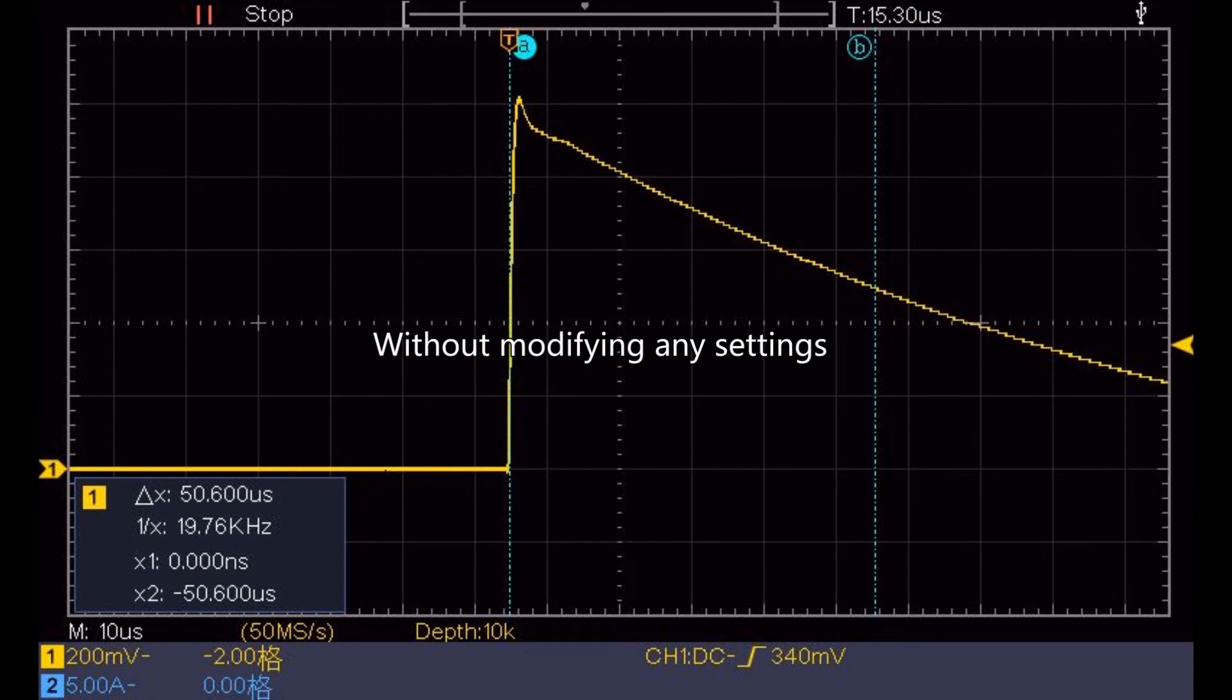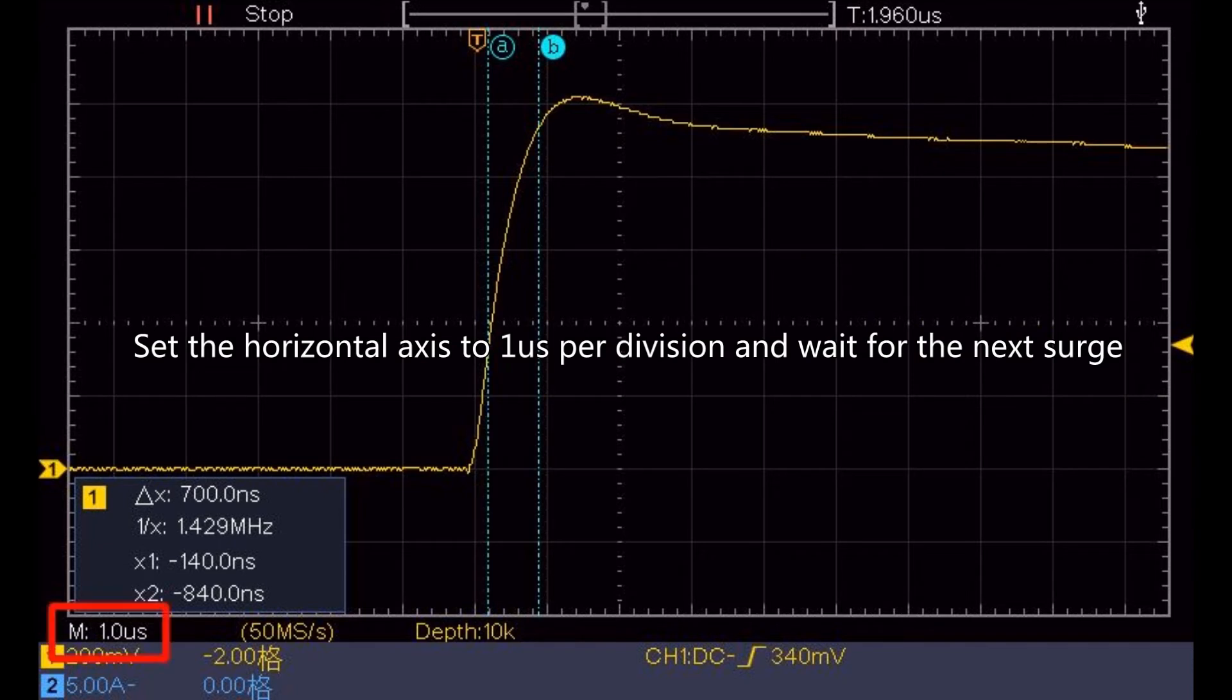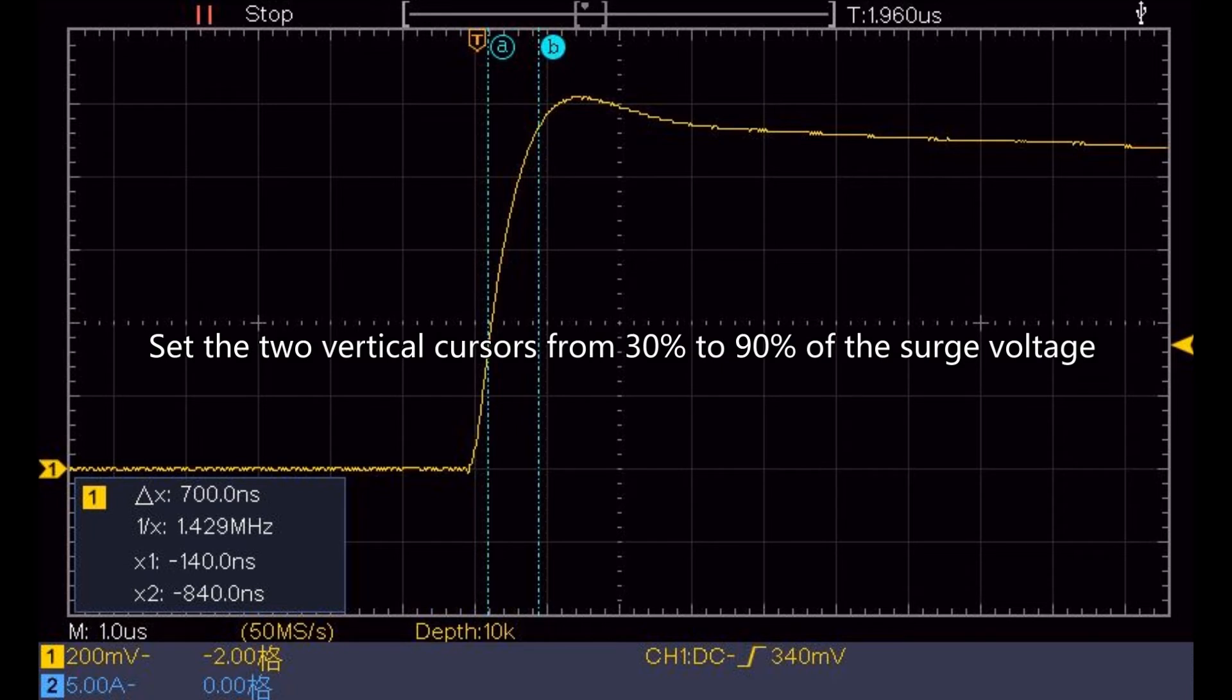Without modifying any settings, use the two vertical cursors to view the time to half value. Set the horizontal axis to 1 microsecond per division and wait for the next surge. Set the two vertical cursors from 30% to 90% of the surge voltage to view the front time.